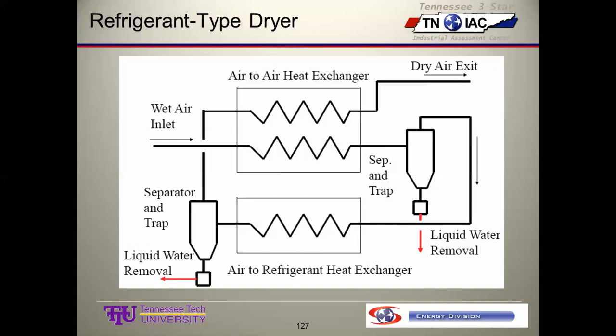The refrigerant-type dryers, as we see in a schematic depicted here, are basically a small refrigeration system, and the air is put across a cooling coil and cooled to someplace between 35 and 38 Fahrenheit. And then it's reheated a little bit before it goes out in the pipes, because if you put 35 to 38 degree air in pipes being distributed around the plant, it's going to sweat like crazy, especially on the outside of the pipe in the summertime when it's warm and humid, and you're going to have drips every place, which would be a safety hazard. So it has to be reheated a little bit. I'd say they probably get it up in the 60s, something like that, which you can put in a pipe, and then you're not going to have any condensate forming on the outside of the pipe just from the ambient air condition.